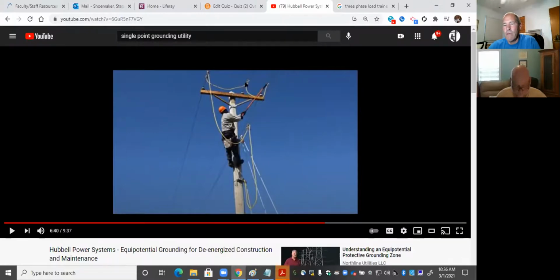Now, if I was to remove the center phase to the far phase first, take this jumper off first, would it be grounded? No, it's not. So you have to flip the process as far as the disconnect is. If I take this jumper off first on the far phase and then take it off the center phase, that jumper remains grounded. So I still have a grounded object on my stick, just in case I lose control of this end, or it comes off the end of the stick and swings around and makes contact with me, it is still grounded. So that's why we do the reverse process in a certain manner.